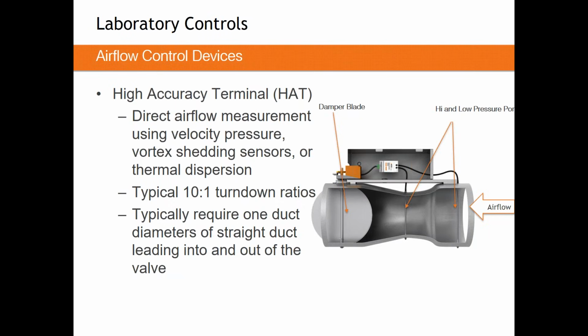5%. So with a VAV box, no manufacturer, when you combine all of the bits and pieces together, will claim an accuracy from minimum flow to maximum flow. With high accuracy terminals, you can get plus or minus 5% accuracy from minimum to maximum flows. So in these critical spaces like labs, ORs, isolation rooms, and compounding pharmacies, you can really readily apply this product pretty much anywhere and get the accuracy you need to pressurize your room as you intend.